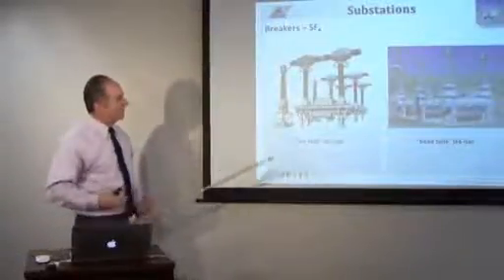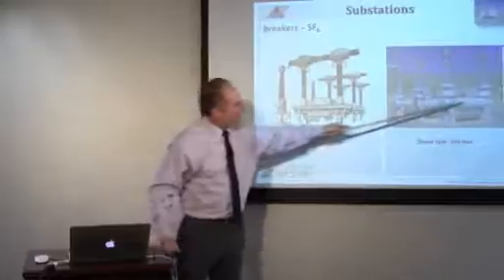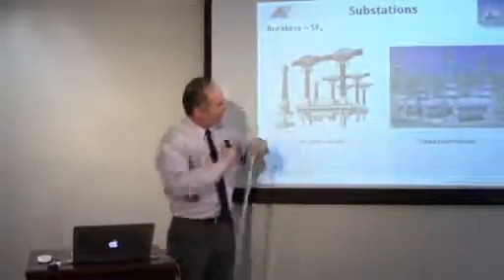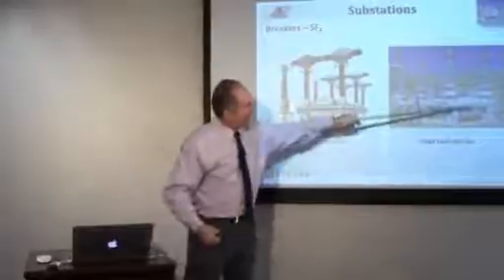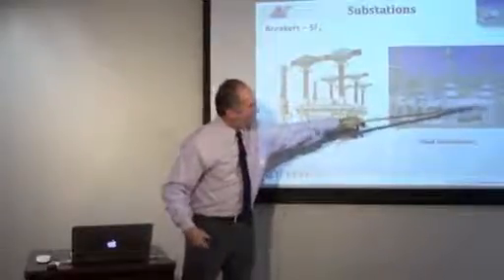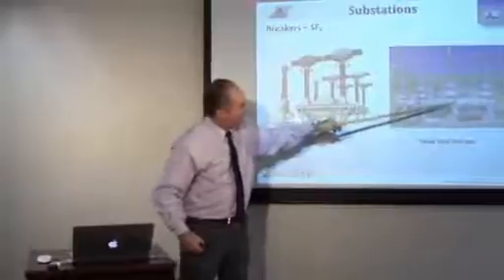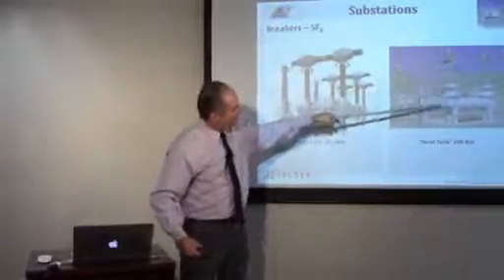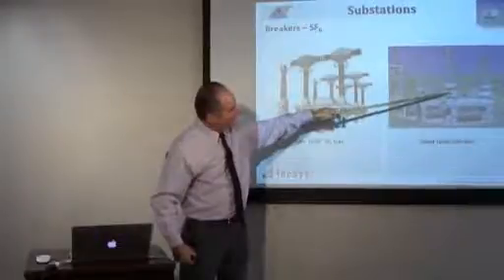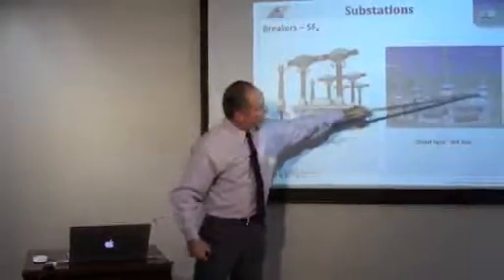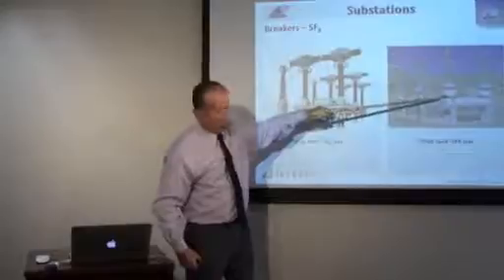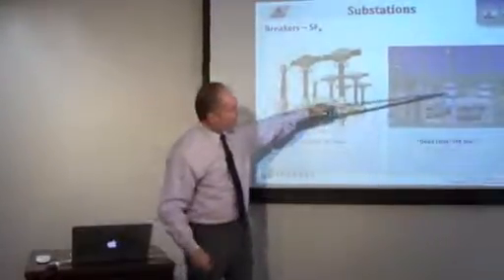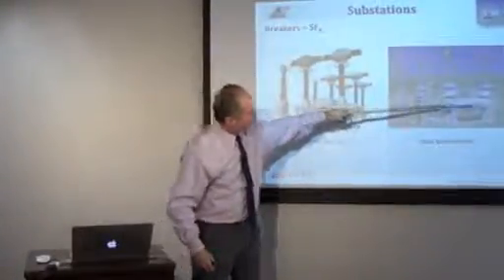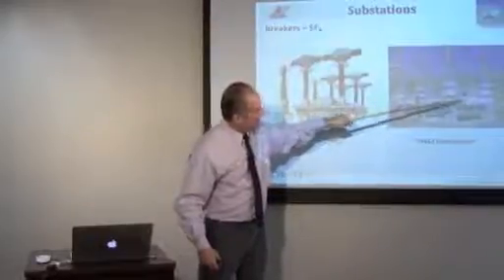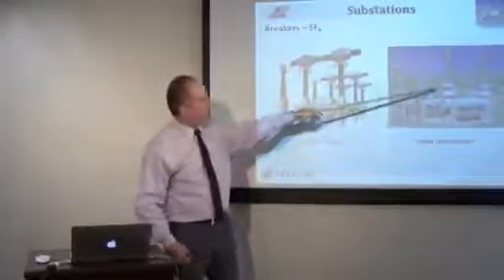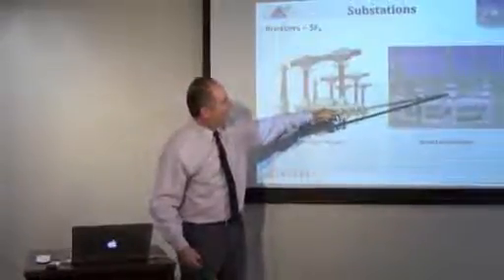Okay, now, here there are two arcing connectors right there, the two connectors in series. It's a manhole plate that you can take the bolts off and inspect. So there's mechanisms here, so the current is going through here. Those are CTs. There are 3 CTs stacked on that bushing and 3 CTs on this one. So that's for protective relays and what have you. That's all the CTs, the donut CTs. Now, the current goes through here. You open the breaker, those contacts open, and current stops flowing. CTs will register 0 power or current flow.